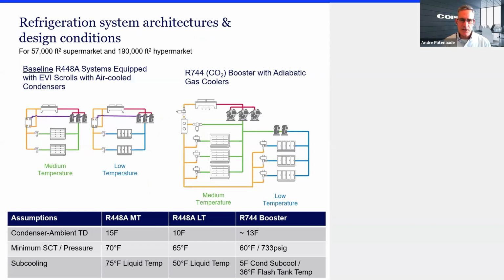So let's take a look at the architectures we're comparing. I mentioned a 57,000 square foot supermarket and a 190,000 square foot one. We've got a 448 system on the left. You can see you've got some small scrolls. That purple line is my enhanced vapor injection line. And you've got a plate heat exchanger, which is providing subcooling. There should be a little expansion valve in this liquid line prior to the plate heat exchanger, so imagine that it's there, and the vapor coming off the heat exchanger goes into the scroll. So that's basically that subcooling effect.